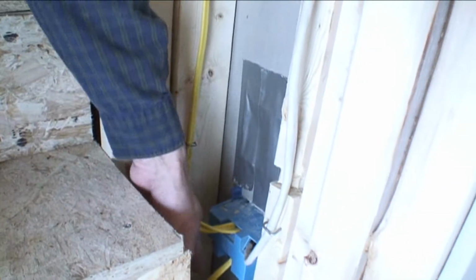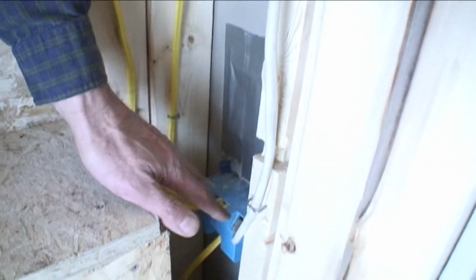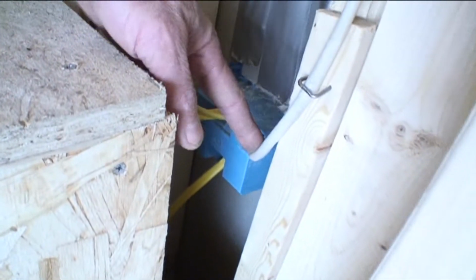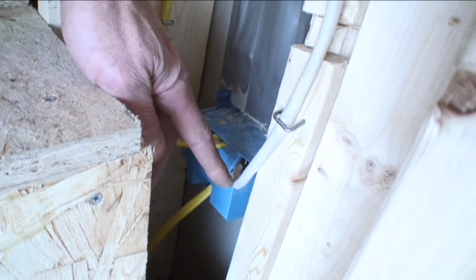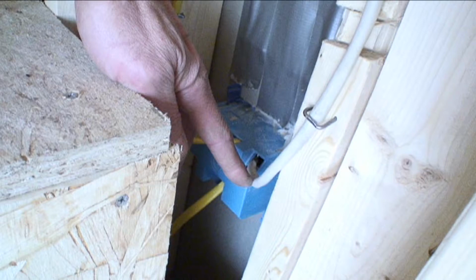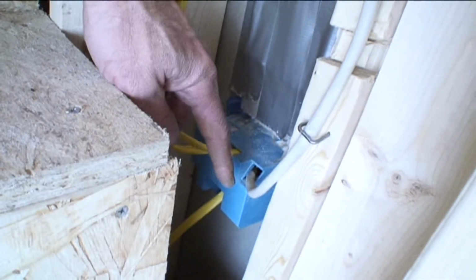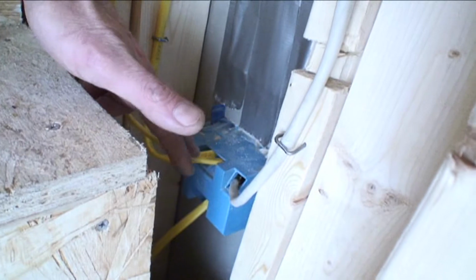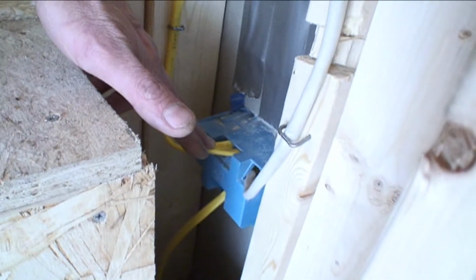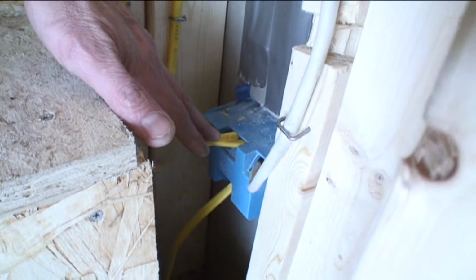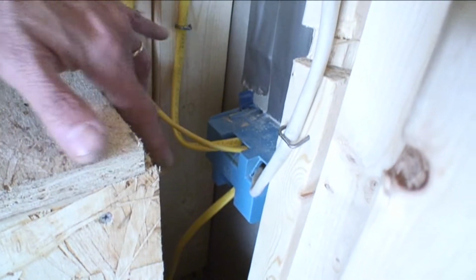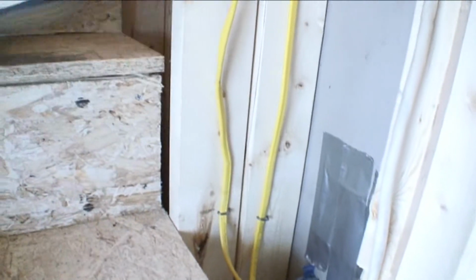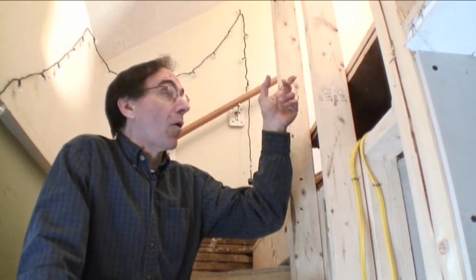There's one line down below here that feeds the box, and then there are 3 wires that come out. This is a 3-way switch—a piece of 3-conductor 14-gauge wire that controls the upstairs light, so you can turn it on from down here or upstairs. Then we have the living room light, which will be a dining room at some point—that's just a standard switch. We also have a feed that goes to the kitchen lighting, and also feeds a small bedroom up here, with a couple outlets in the bedroom and a single outlet in the hallway.